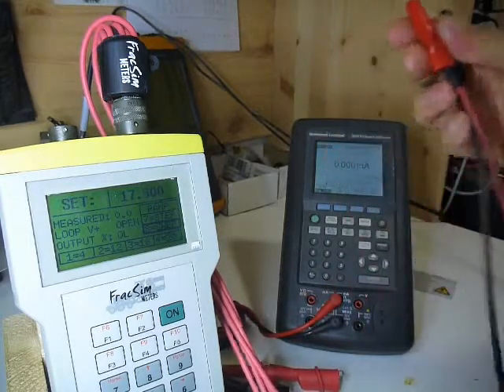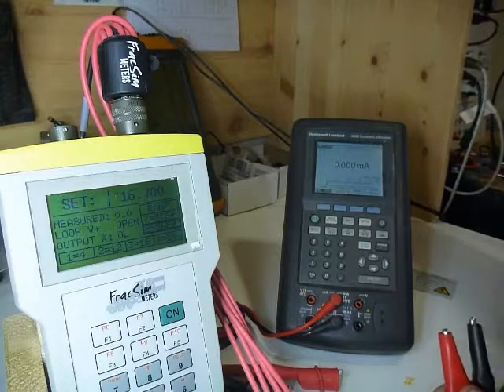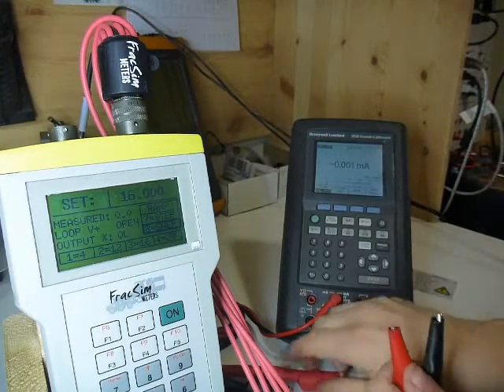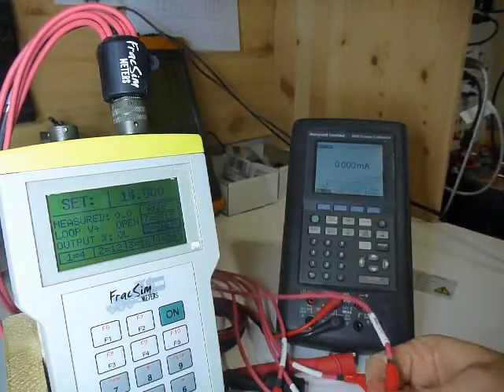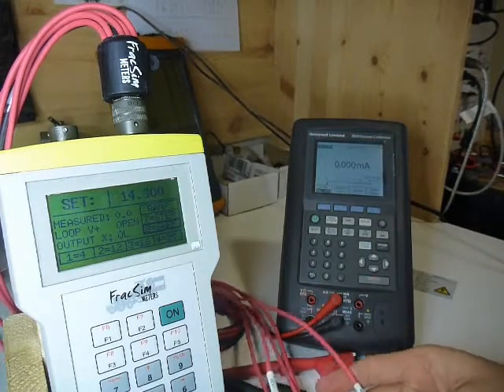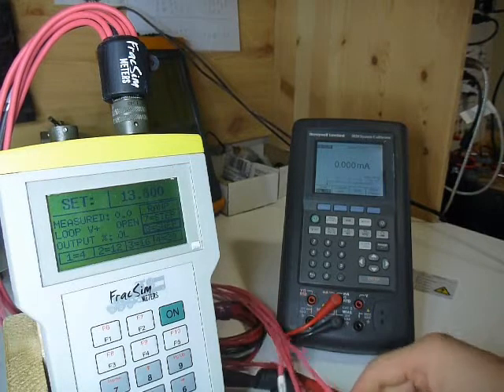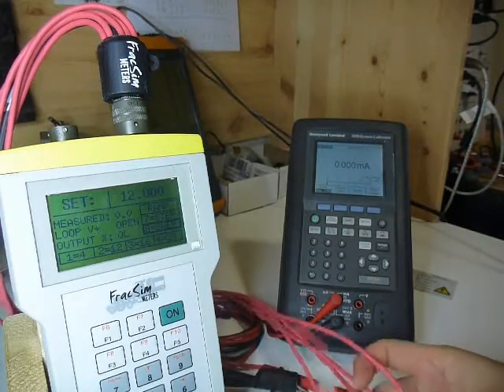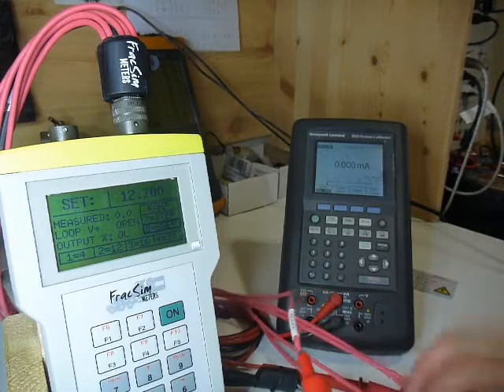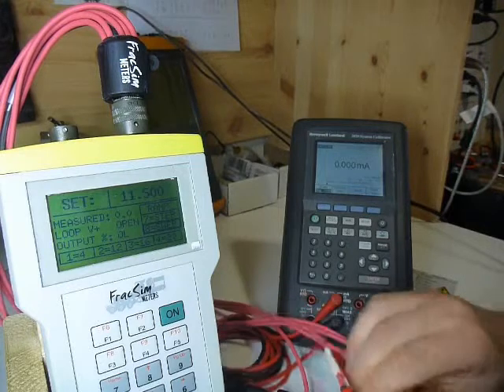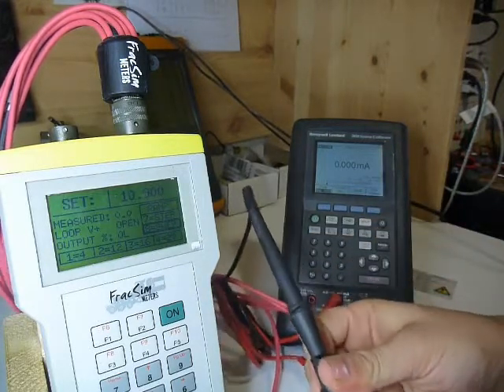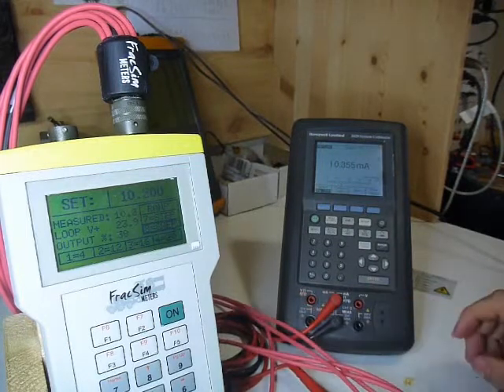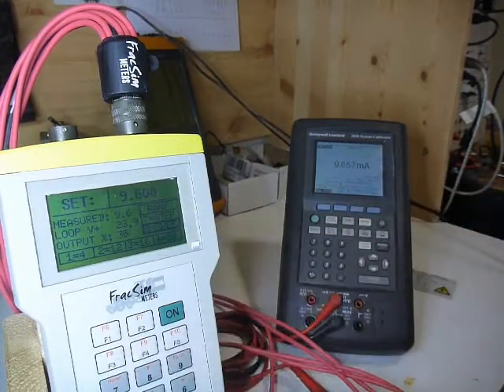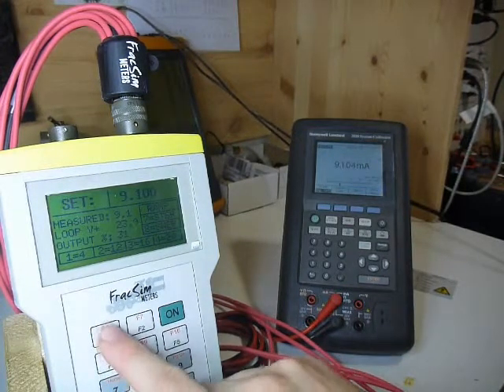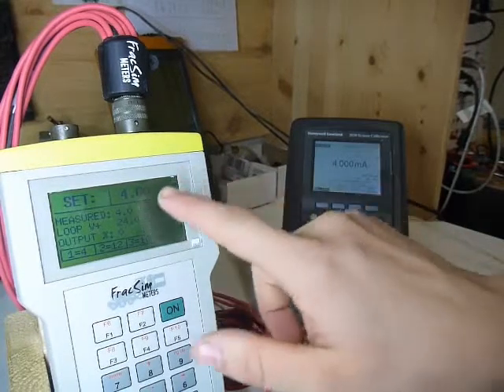So 24 volts from the power supply, which I have to turn up, I'm at 8 volts right now. So 24 volts is going to go into the Fracsim on the one labeled 24 volts. And current sim is going to return to the Fluke here, just so we can look at the value, and then the other side of the Fluke is going to go to the power supply ground. And we're still in ramp mode, so you can see there. I'm going to turn the ramp off, or the sweep off, and go to 4 milliamps again. So you can see we're back at 4 and 4.